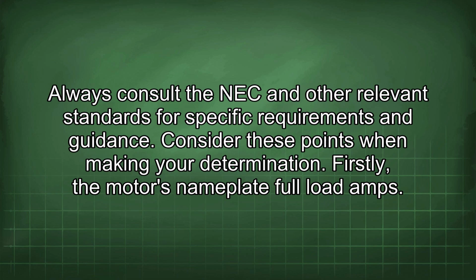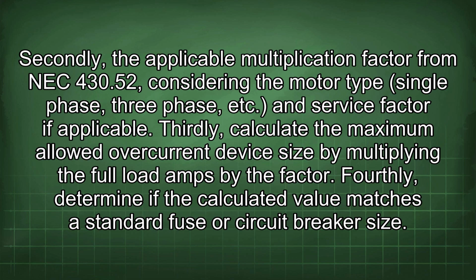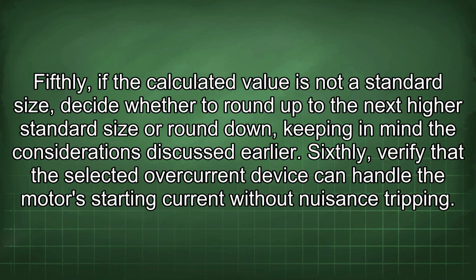Firstly, the motor's nameplate full load amps. Secondly, the applicable multiplication factor from NEC 430.52, considering the motor type, single-phase, three-phase, etc., and service factor if applicable. Thirdly, calculate the maximum allowed overcurrent device size by multiplying the full load amps by the factor. Fourthly, determine if the calculated value matches a standard fuse or circuit breaker size. Fifthly, if the calculated value is not a standard size, decide whether to round up to the next higher standard size or round down, keeping in mind the considerations discussed earlier.